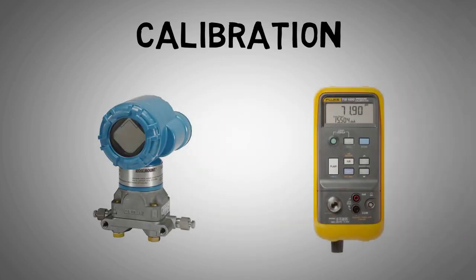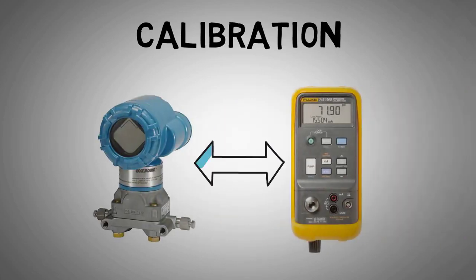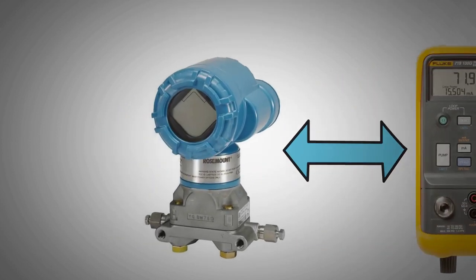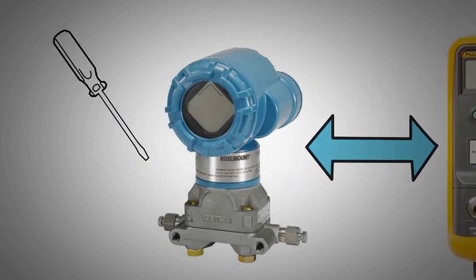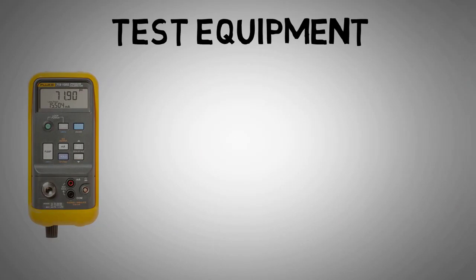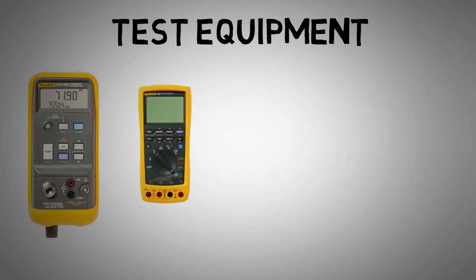Calibration is the process of comparing plant instrumentation to a known quantity to check for the instrumentation's accuracy. Adjustments are then made if the accuracy of the equipment is out of its allowed tolerance. The known quantity instrumentation is checked against is usually in the form of test equipment that is regularly calibrated to a high degree of accuracy.